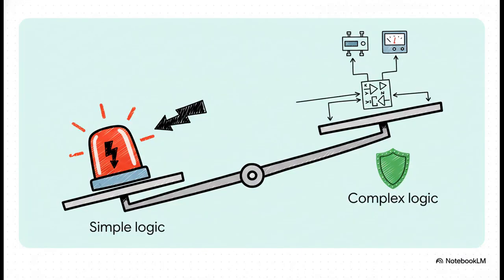And this design really gets at a critical engineering idea, asymmetric logic. The logic for the danger signal, the red light, is deliberately simple and hypersensitive. It's just a direct measurement right at the inverter. Easy. But the safe signal, the green light, it has a much higher burden of proof.